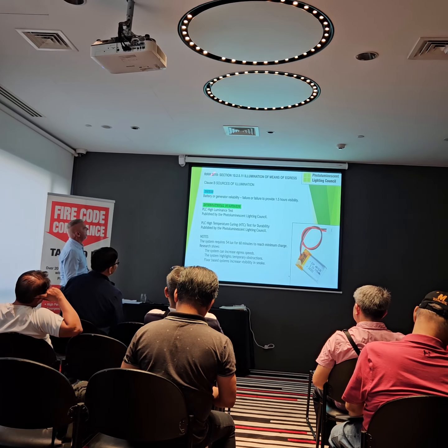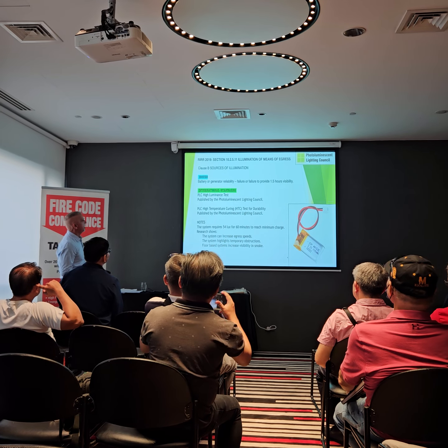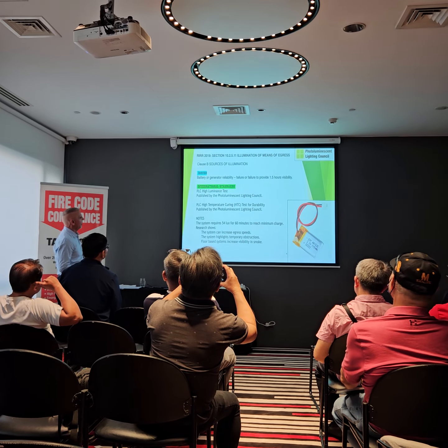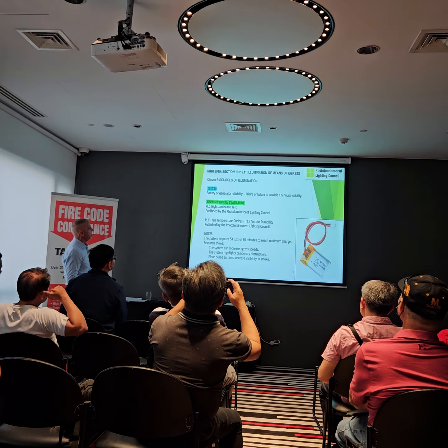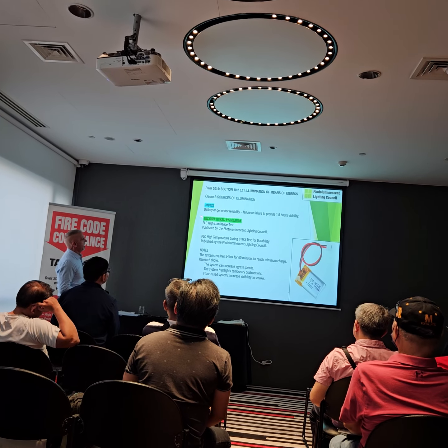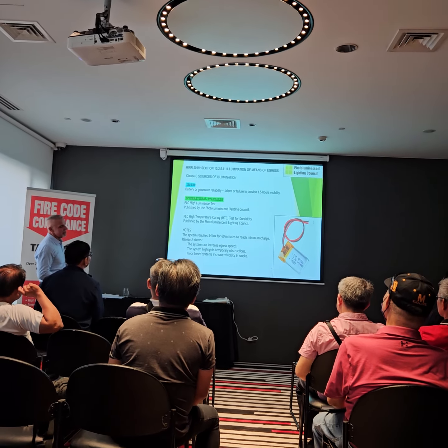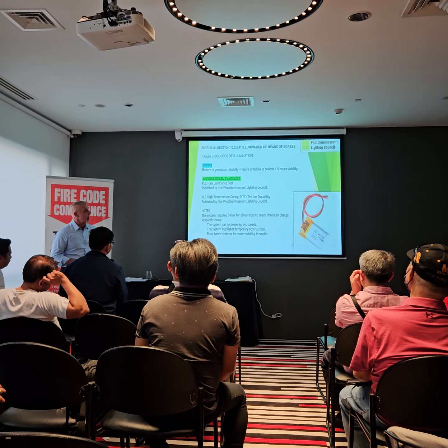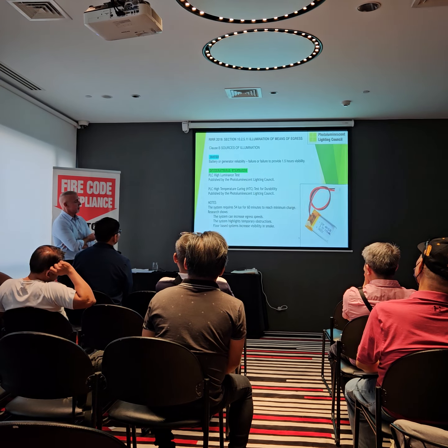Okay, clause B, sources of illumination, talks about reliability and needs to go for 1.5 hours. I think I mentioned earlier, there are reliability issues, especially if systems aren't well maintained, with generators for sure.